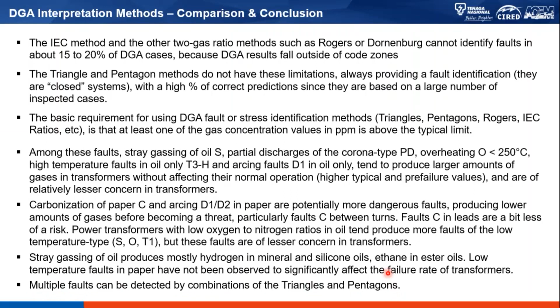And the last one, based on the report, is the multiple faults that can be detected by the combination of triangles and pentagons. If you use them side by side, you will have more information in terms of complementary or more detailed explanation of the fault occurring inside the transformer.